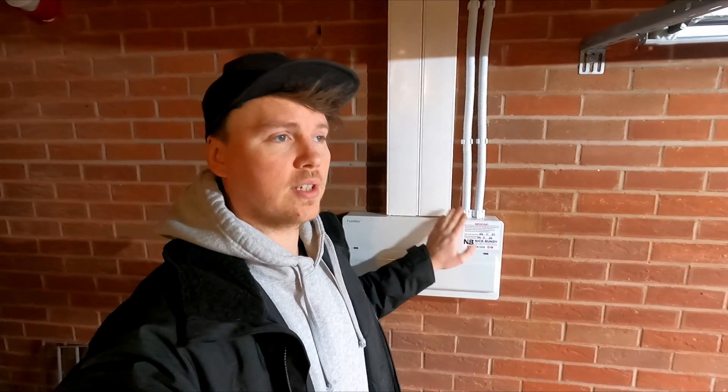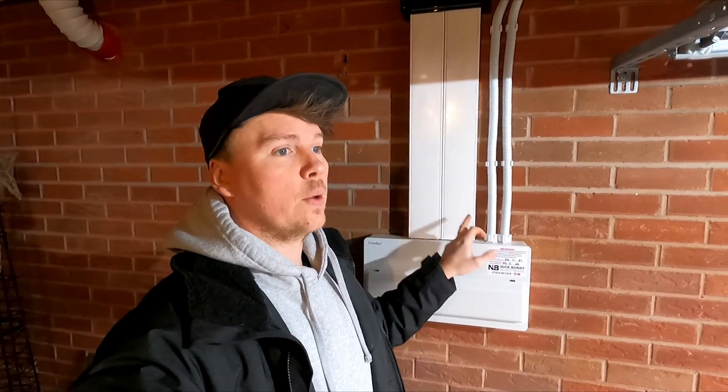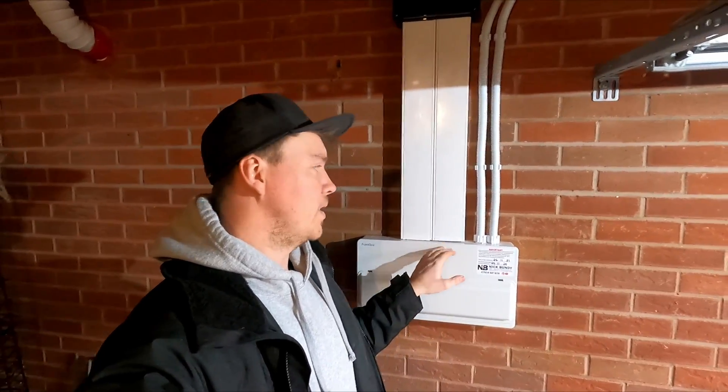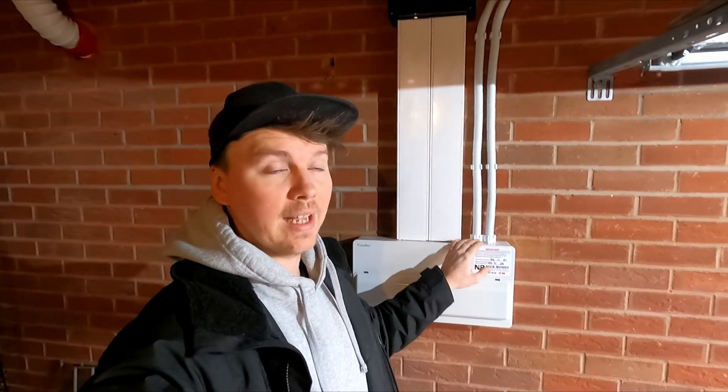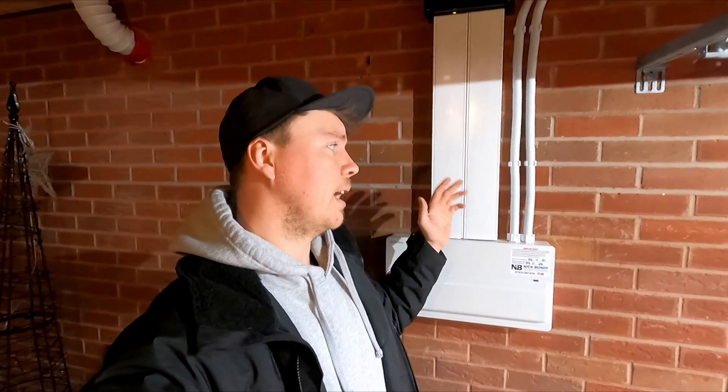In here we have the conduit - live and neutral go through separate holes in the metal fuse board. Obviously to some guys that don't know this: a lot of people say that with the electromagnetic effects of putting the live and neutral into separate holes in a metal consumer unit or adaptable box, because of the eddy currents and the magnetic field each conductor creates, they say if you ever do this you should make a slot between the two holes to conjoin them, which will then cancel the field out. John Ward did a fantastic video on this where he actually measured the magnetic field and whether anything heated up, and his conclusion was it made no difference whatsoever. I'll put a link below if I can find it.